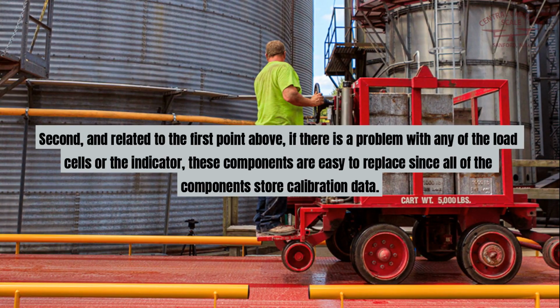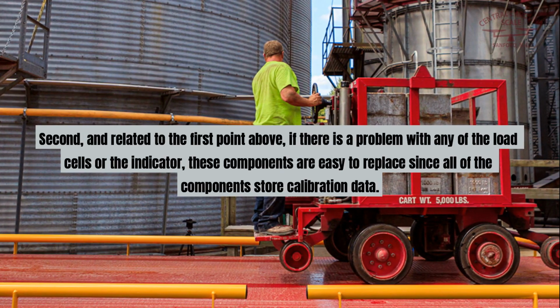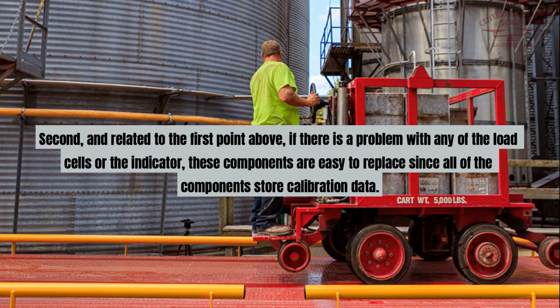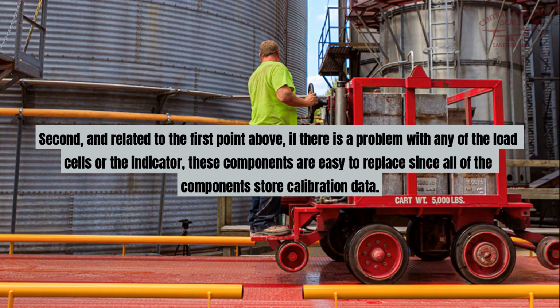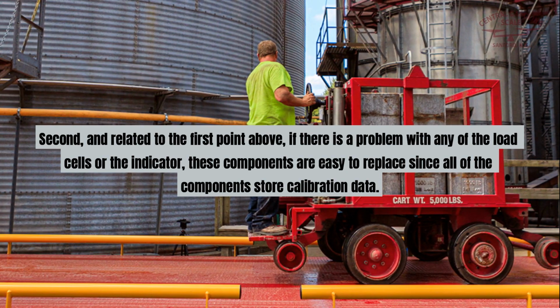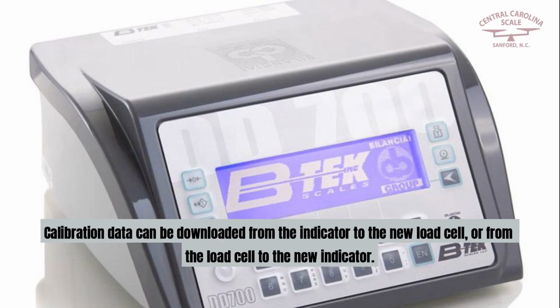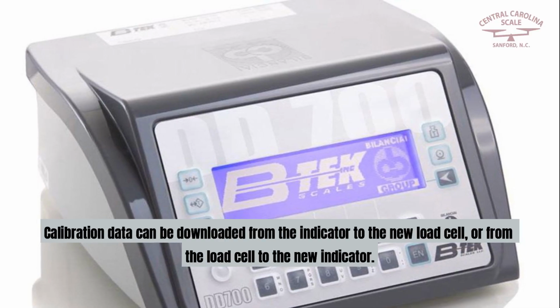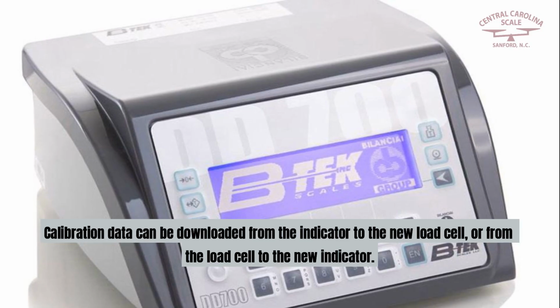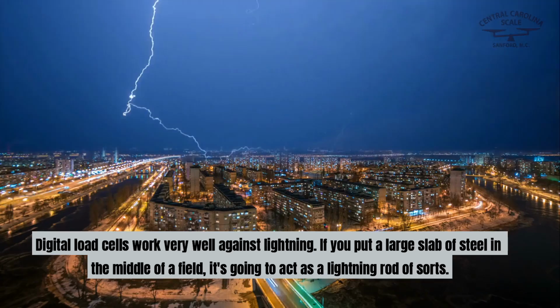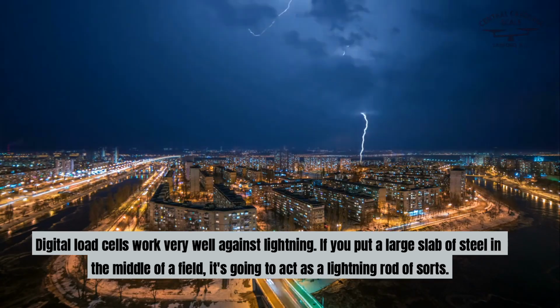Second, and related to the first point above, if there is a problem with any of the load cells or the indicator, these components are easy to replace since all of the components store calibration data. Calibration data can be downloaded from the indicator to the new load cell or from the load cell to the new indicator. Digital load cells work very well against lightning.